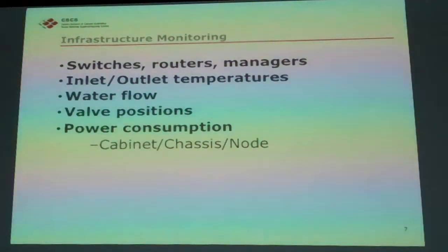We had no clue that was even happening. We stumbled on this. Now we're putting it in as a check to see if we have an issue. So that module's been removed and is being repaired. But it's just an indicator, something that you wouldn't think to monitor is the power consumption. But it's a very simple test, and it can be very important.